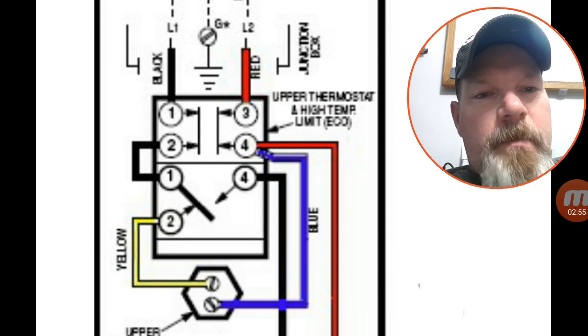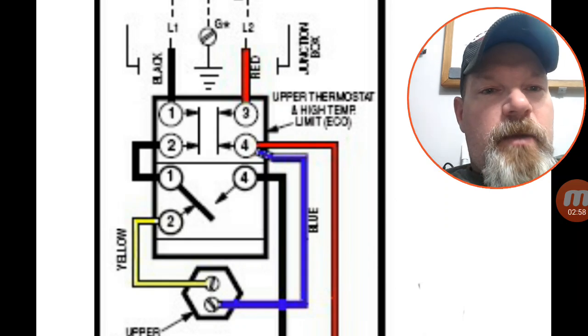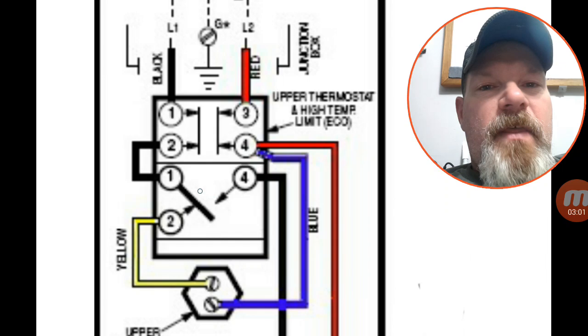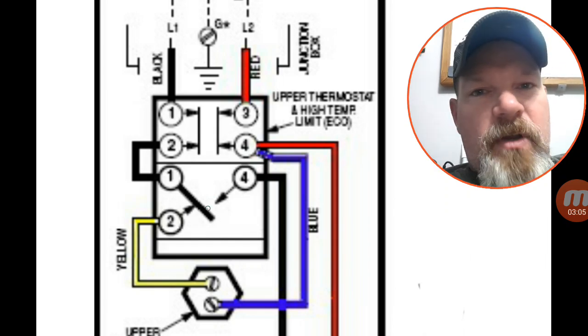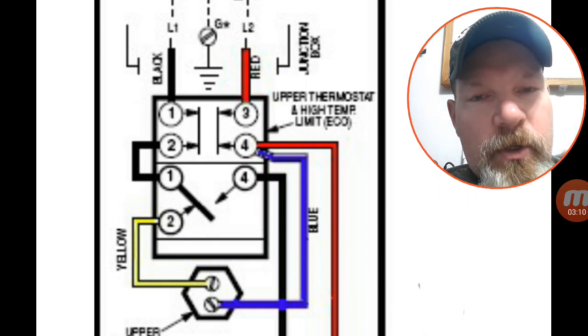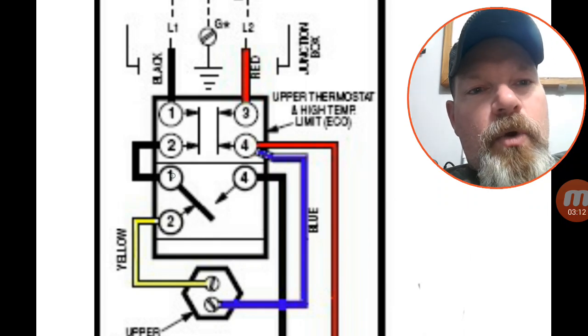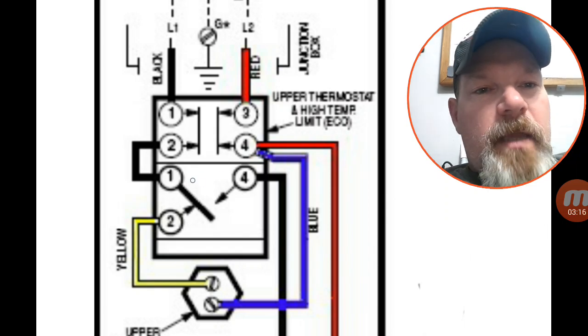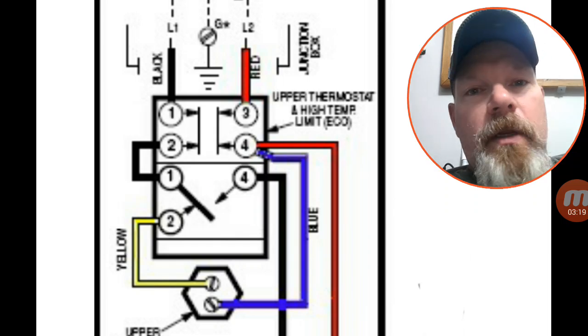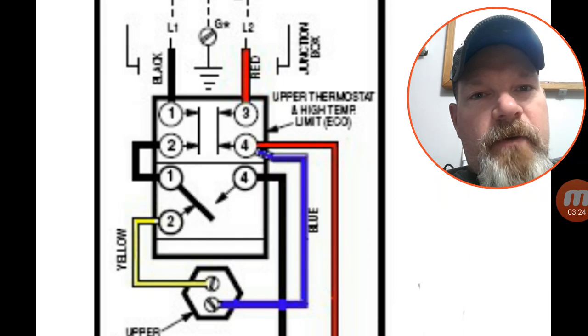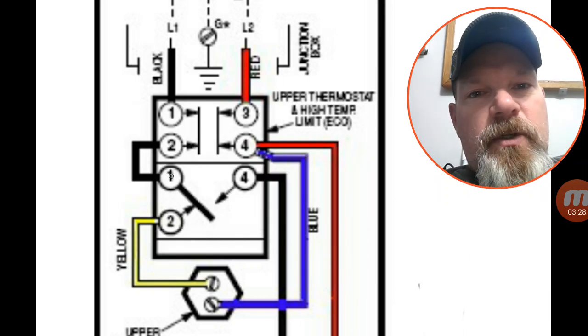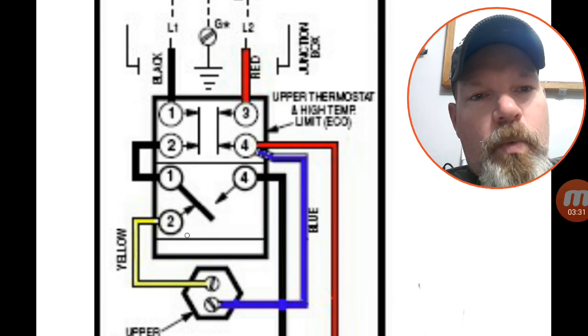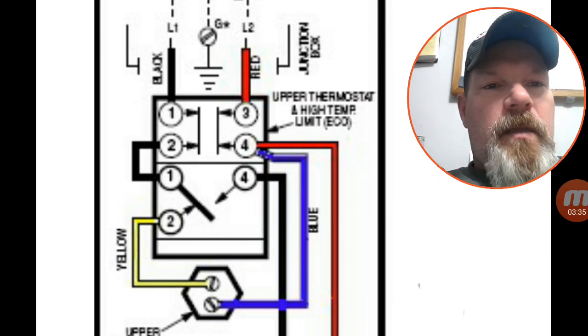This is your thermostat, so it's either going to send power to the upper element or it's going to send power to the lower element. If the thermostat is satisfied, meaning it does not have a call and it's in its natural or normal position, it's going to be normally closed between one and four. That is the normally closed position, or also could be termed as not a call for heat. If it does have a call for heat, it's going to close one to two.